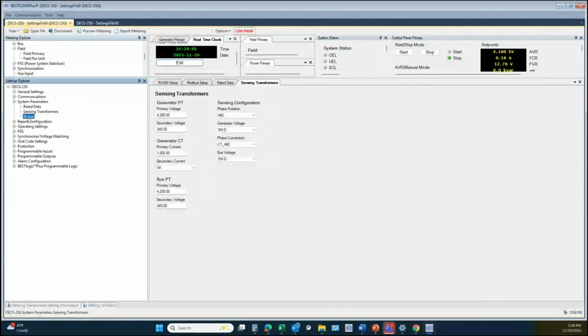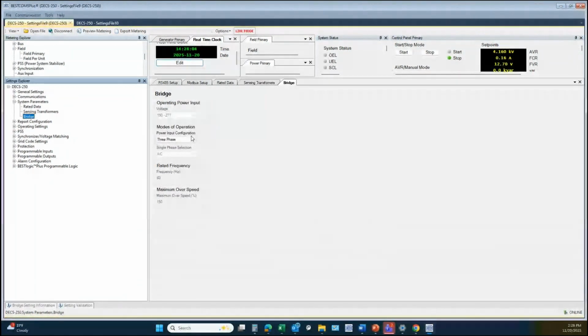And then moving on, we go to the bridge settings. With the DECS 250, the only option here that you can actually change is the power input configuration, whether you're using like a single phase PMG, or maybe you're using a DC source for the DECS 250 for operating power, or if you're bringing in a 3-phase source for the operating power. Single phase versus 3-phase or versus DC will affect the field forcing capability of the DECS 250.